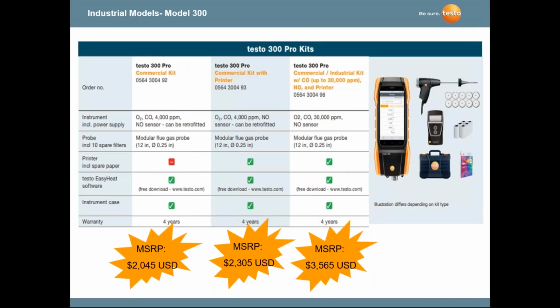If you want to measure NOx, then you get into what we call our Pro Series or an Industrial Series. And you'll see that it has the capability of measuring oxygen and CO up to 4,000 ppm, and it can be retrofitted with an NO sensor. It doesn't come with one at the time of shipment, but it can be upgraded at a later date. The far right one here comes with the NO sensor included, which means that you really have three sensors: O2, CO, and NO. And this higher end model here at 3565 also has a sensor and a dilution, an extra pump inside the instrument that allows us to measure up to 30,000 parts per million in CO. Again, for those industrial guys, high-end commercial guys that are tuning boilers for maximum combustion efficiency.